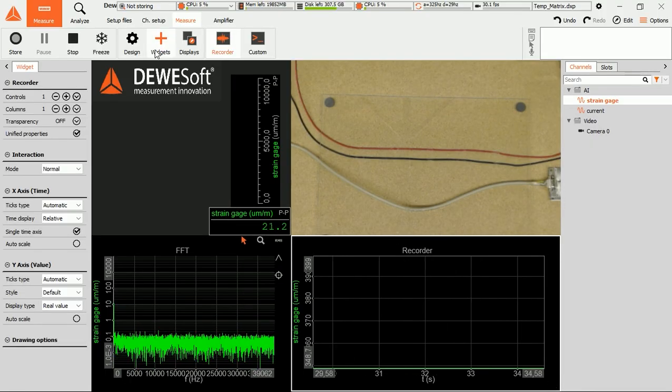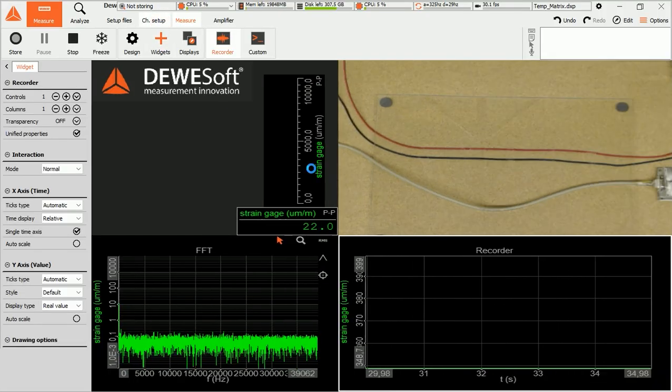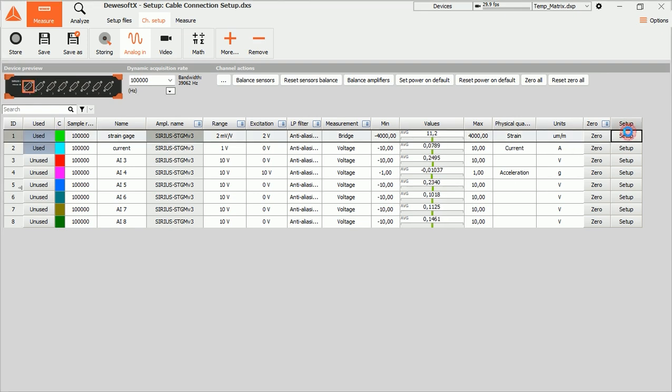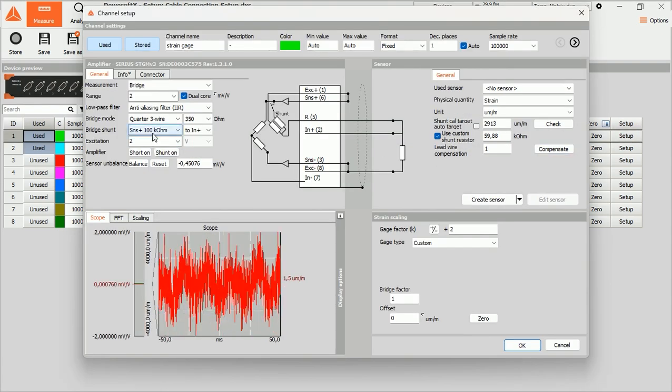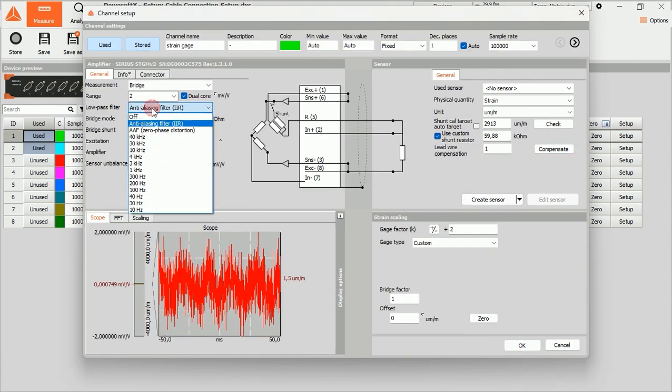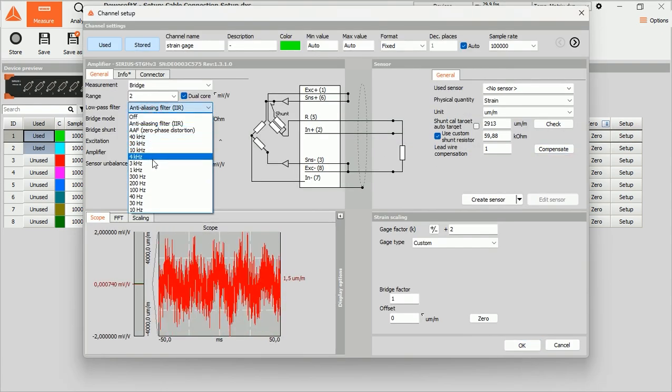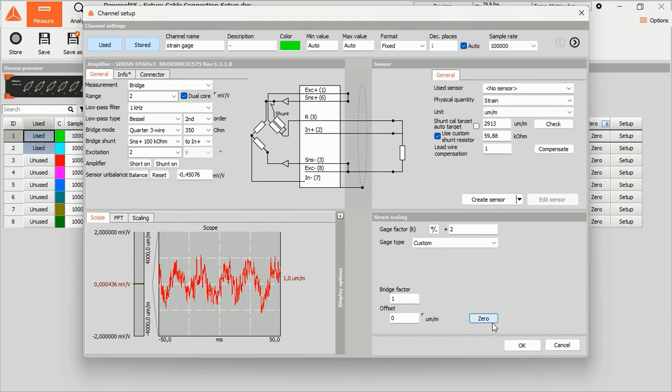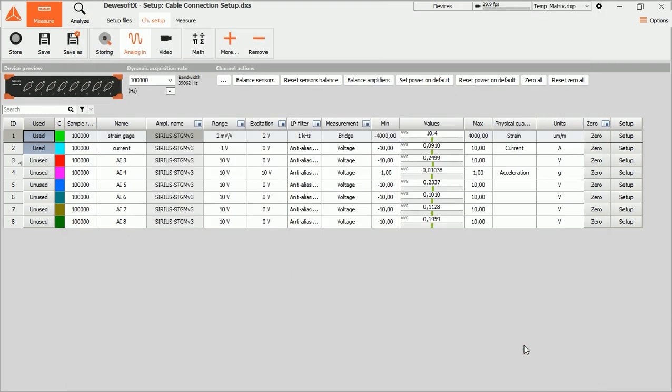Now that we have first optimized our cabling, we can now apply a filter on the analog input signal. Of course, first we should ensure that our useful signal doesn't contain any components higher than 1 kHz.